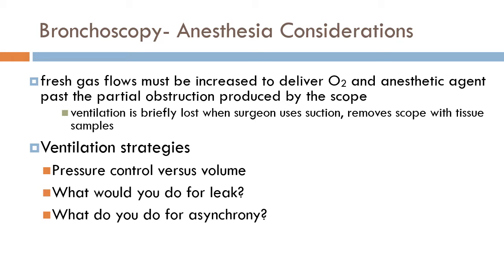Pressure, so in that setting, and you have a shared airway where I had a little hole, and the water is going to drip, drip, drip out, and not come back to the ventilator. The machine's going to give 500, and it's going to alarm because it is watching on the way back and say, tidal volume's not achieved, right? But it knew it gave 500. So that 500 doesn't actually get to where it needs to go, which is where? Where's the real destination that we're trying to send the oxygen to? Alveolar capillary membrane, right? We're going to jump across that little thin layer and get into the blood. It doesn't care. It's just going to keep ventilating that way. Its cutoff is simply, I gave 500, deal with it.